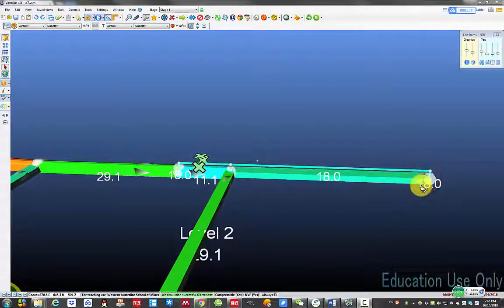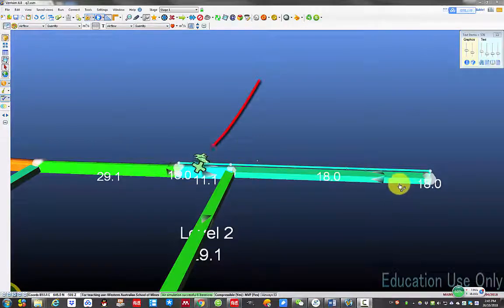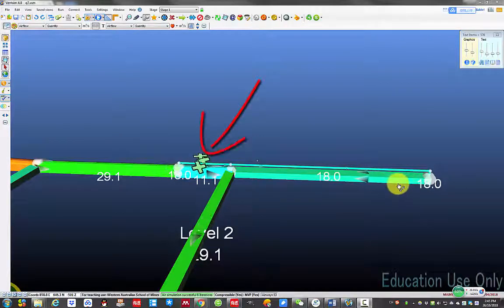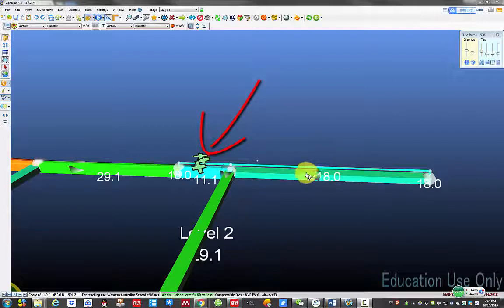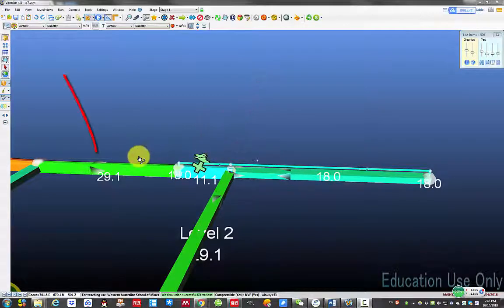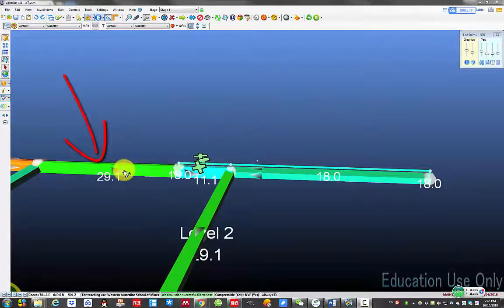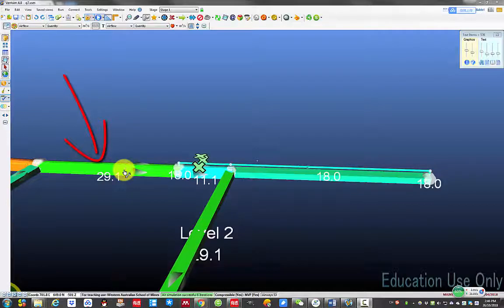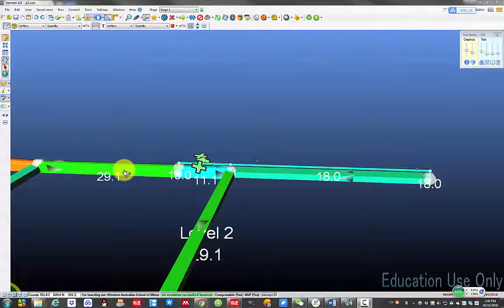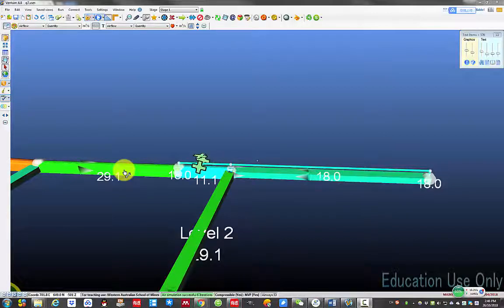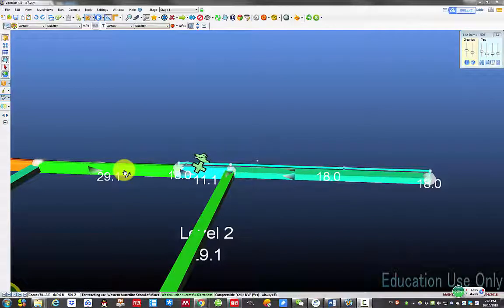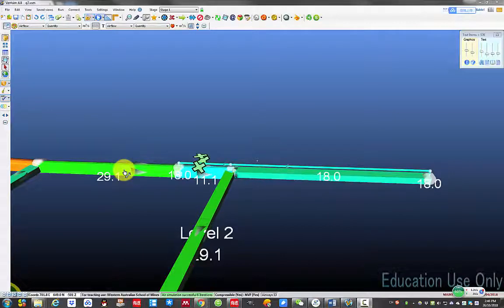The second point we need to consider is you need to make sure the airflow provided by the auxiliary fan needs to be less than the air available in the airway where the fan is located. Generally, the airflow in the airway needs to be 30 percent higher than the amount of air the fan is trying to push. This is to prevent air recirculation.